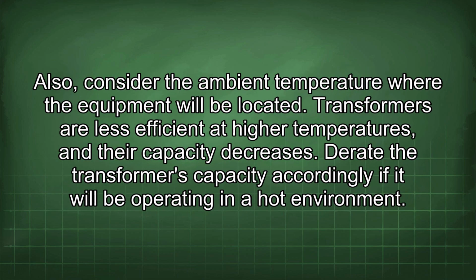Also, consider the ambient temperature where the equipment will be located. Transformers are less efficient at higher temperatures, and their capacity decreases. Derate the transformer's capacity accordingly if it will be operating in a hot environment.